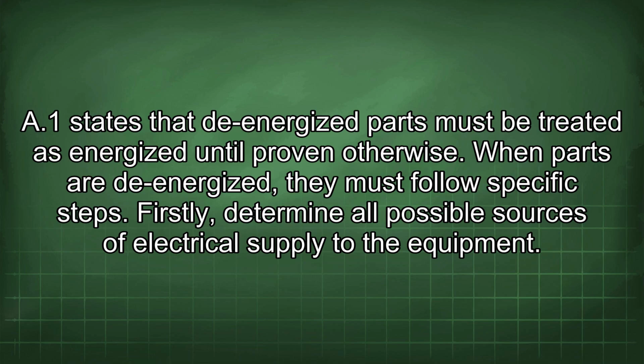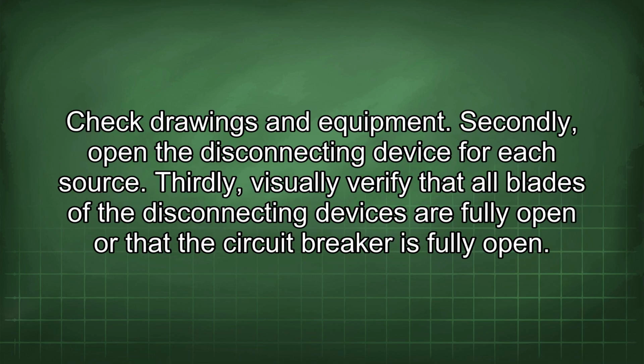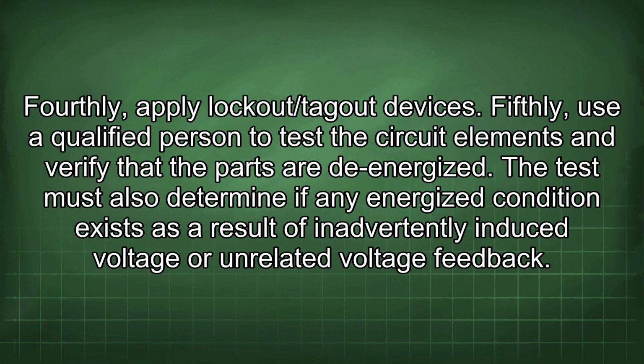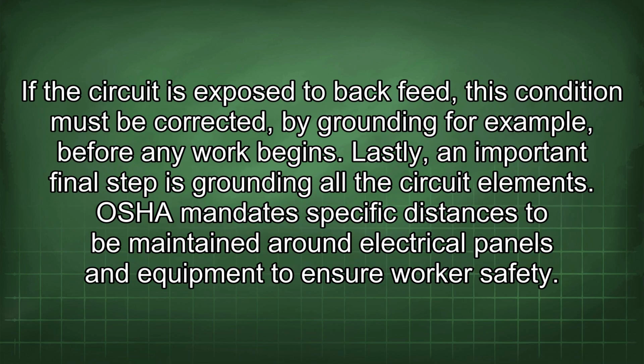Firstly, determine all possible sources of electrical supply to the equipment. Check drawings and equipment. Secondly, open the disconnecting device for each source. Thirdly, visually verify that all blades of the disconnecting devices are fully open or that the circuit breaker is fully open. Fourthly, apply lockout/tagout devices. Fifthly, use a qualified person to test the circuit elements and verify that the parts are de-energized. The test must also determine if any energized condition exists as a result of inadvertently induced voltage or unrelated voltage feedback. If the circuit is exposed to backfeed, this condition must be corrected by grounding, for example, before any work begins. Lastly, an important final step is grounding all the circuit elements.